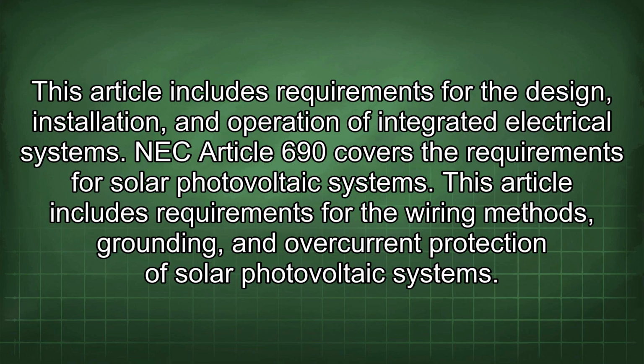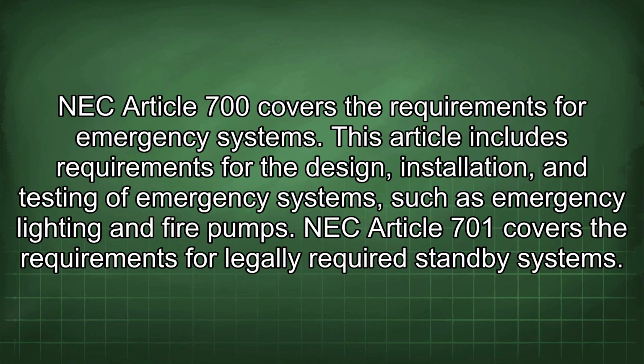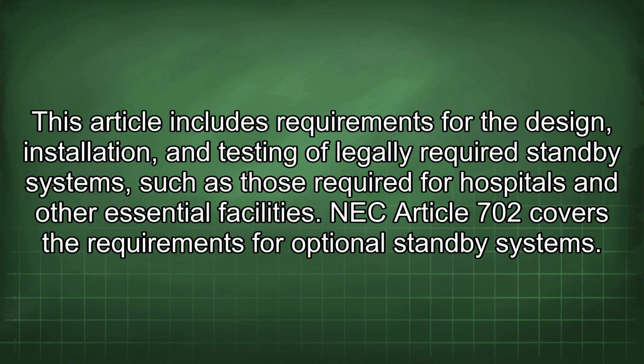NEC Article 690 covers the requirements for solar photovoltaic systems. This article includes requirements for the wiring methods, grounding, and overcurrent protection of solar photovoltaic systems. NEC Article 700 covers the requirements for emergency systems. This article includes requirements for the design, installation, and testing of emergency systems such as emergency lighting and fire pumps. NEC Article 701 covers the requirements for legally required standby systems. This article includes requirements for the design, installation, and testing of legally required standby systems, such as those required for hospitals and other essential facilities.